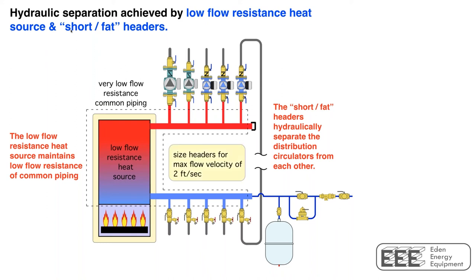My suggestion when sizing headers in a system like this with five circulators: assume they're all on simultaneously — which they could be under design load — figure out the total flow rate, and then size your header for a flow velocity that doesn't go above two feet per second. That's definitely going to be at least one pipe size larger than what you might be used to, but that is the concept of keeping head loss to an absolute minimum. If you do that, you don't need closely spaced T's and you don't need a separate component called a hydraulic separator, because the heat source and headers in combination are doing it for you.